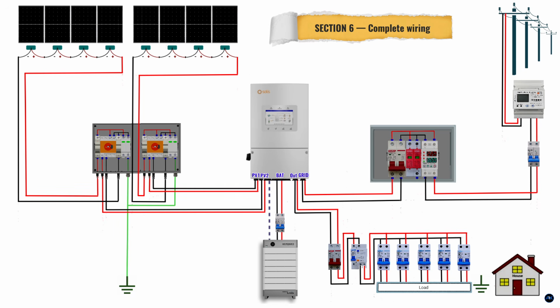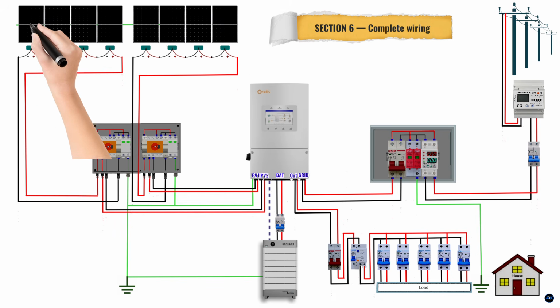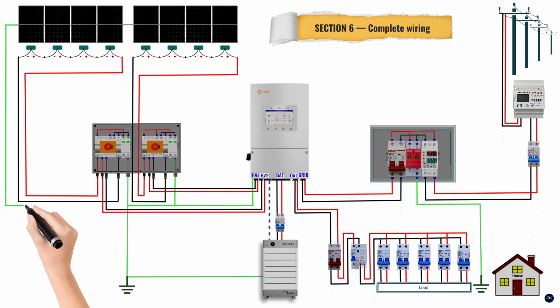Step 5. Earthing. Every metal surface in this system must connect to a single earth point. Drive a copper earth rod at least 1.2 meters into the ground. Test resistance, below 10 ohms. 16 millimeter squared green-yellow cable from that rod to your main earth bar. Everything connects there. Panel frames to combiner earth bar. Combiner box to main earth bar. Inverter PE terminal to main earth bar. Battery rack bonded. All AC circuit earths to the AC/DB earth bar. All paths meet at one point, one connection to ground. Test continuity between every metal component and the earth rod before energizing anything.